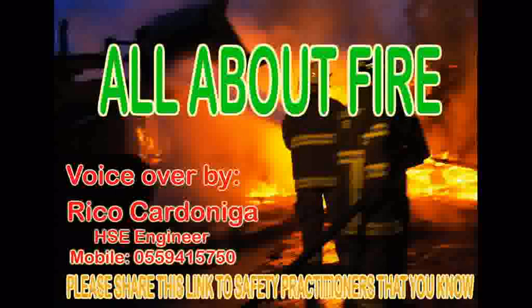Conduction. This is the transmission of heat through a material with sufficient intensity to melt or destroy the material and ignite combustible materials which come into contact. Radiation. Often in a fire, the direct transmission of heat through the emission of heat waves from a surface can be so intense that adjacent materials are heated sufficiently to ignite. Direct burning. This is the effect of combustible materials catching fire through direct contact with flames, which causes fire to spread.